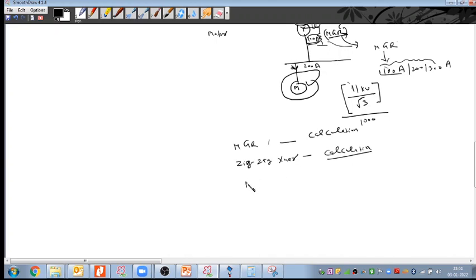And then there is another type of NGR, called the neutral grounding reactor. This is a reactor, not a resistance, and we use it in extra high voltage, I can say ultra high voltage substations, at 400 kilovolt and above, not below this. It is used between the shunt reactor and the ground in order to allow the single pole auto reclosing, SPAR.